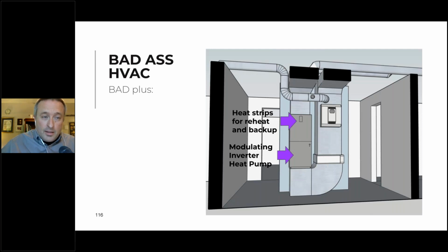So BAD ASS is a BAD plus the modulating inverter heat pump that we already talked about, and heat strips for reheat. And if you size aggressively, those will also cover you in your very cold temperatures. And then also a humidifier for climates and clients where that makes sense. That needs to be controlled by an outdoor temperature sensor, because the humidity really needs to get dialed down when it gets very cold outside.